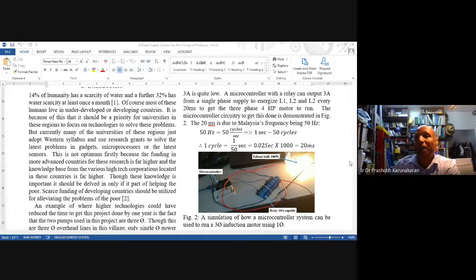There's no problem getting 3 amps out of a single phase. Single phase homes typically have somewhere between 20, 30, 40 amps available. If you turn on all the aircons, it will be about 40 amps, so 3 amps is no problem at all. Every 20 milliseconds you energize the red phase at 3 amps, the next 20 milliseconds the yellow phase, and the next 20 milliseconds the blue phase. That way you can run a 3-phase motor.